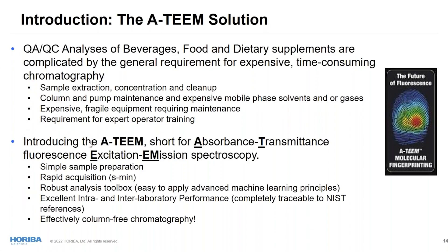What we call the A-TEEM is short for Absorption Transmittance fluorescence Excitation Emission spectroscopy. The main advantages are speed — seconds to minutes acquisition — very robust analysis, toolboxes for advanced machine learning principles, and excellent inter- and intra-laboratory performance. We've recently completed an ASTM method for the water industry as evidence of relative performance. It's also known as column-free or optical chromatography.